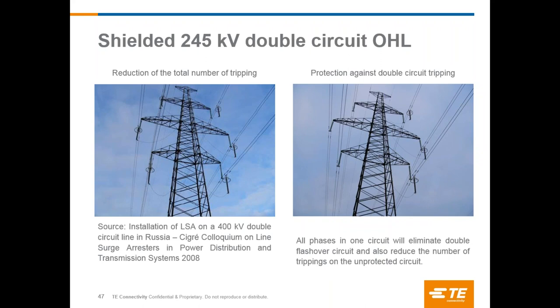And on the right side, you have protection against double circuit tripping, in which you have arresters installed on all phases of just one circuit.